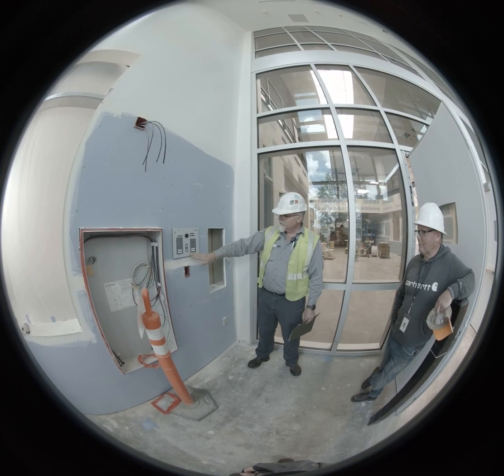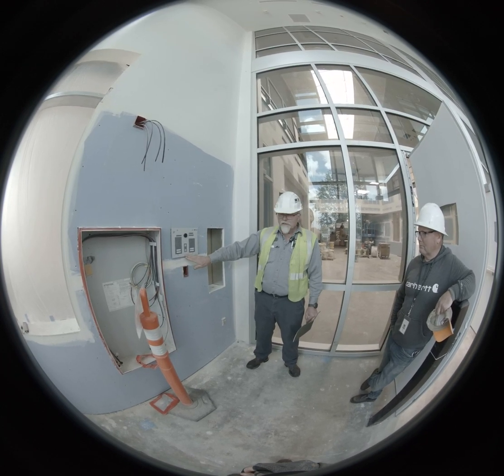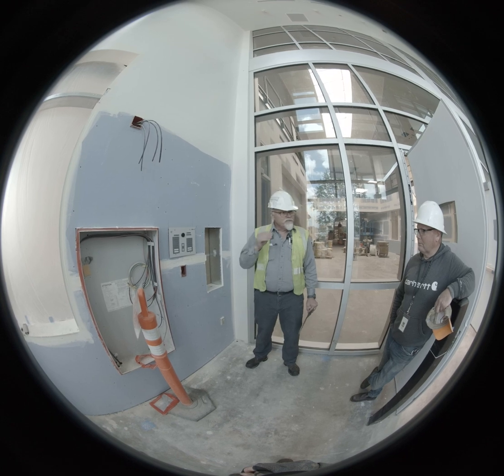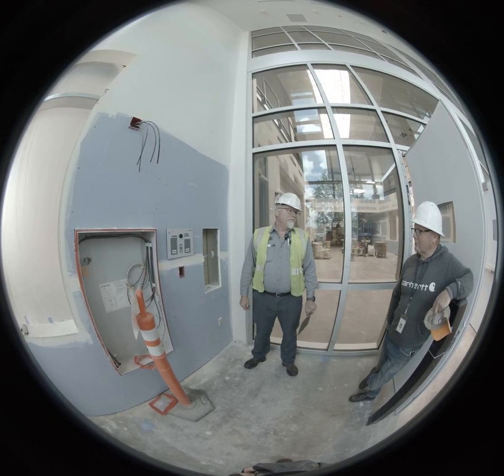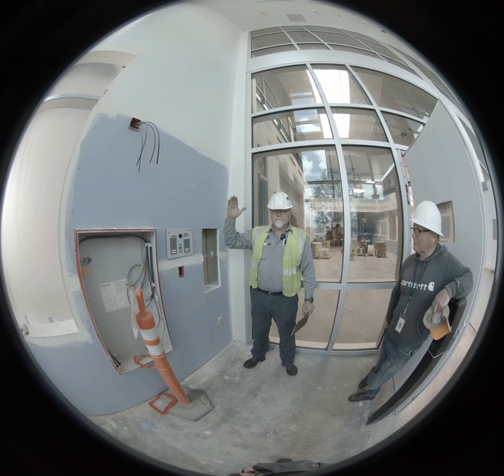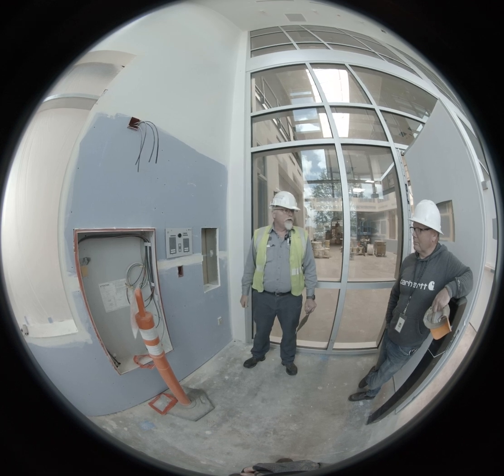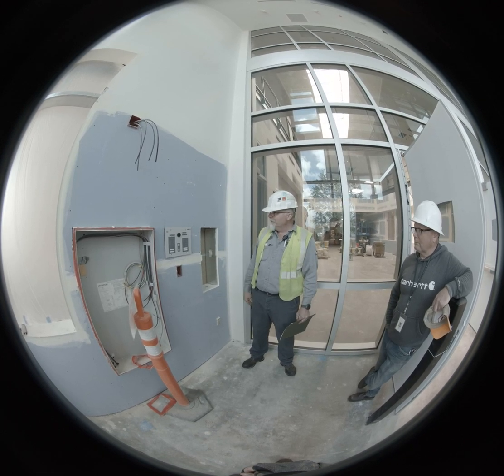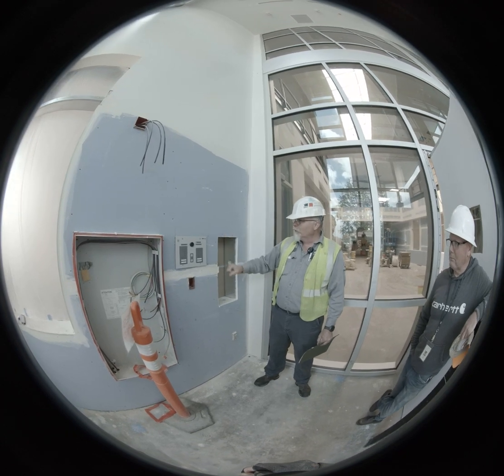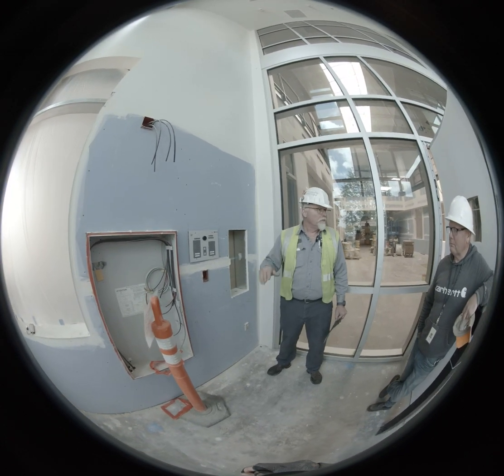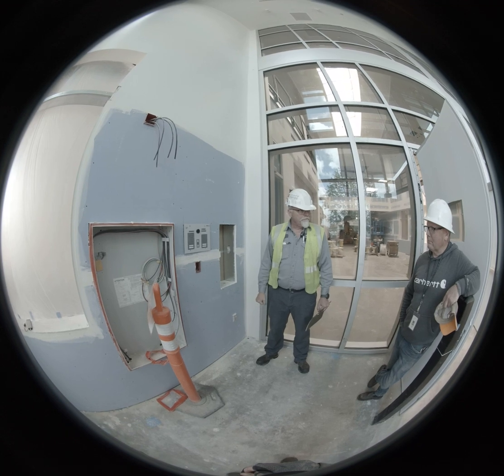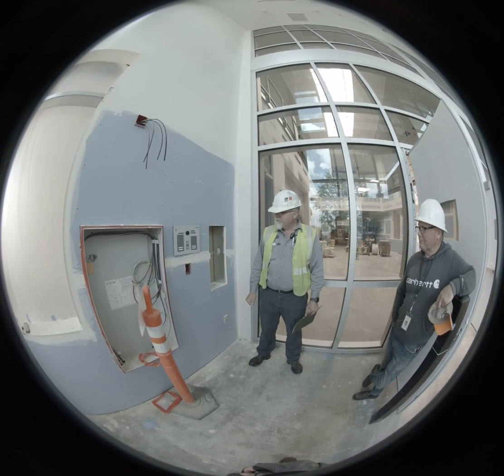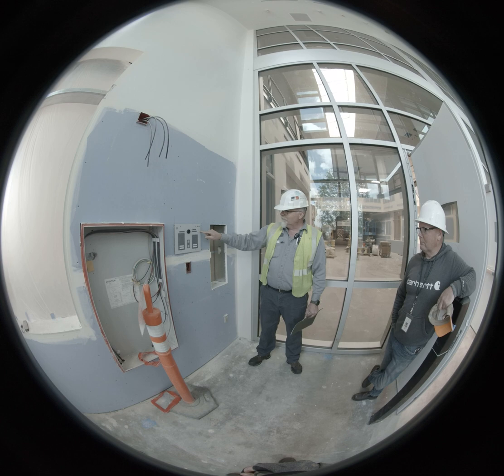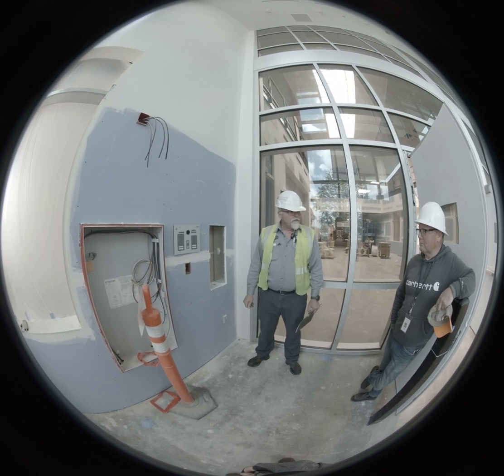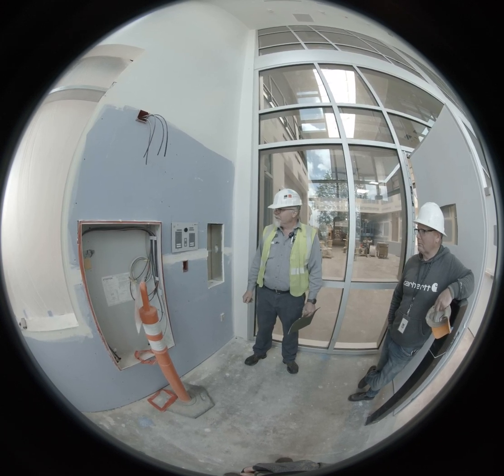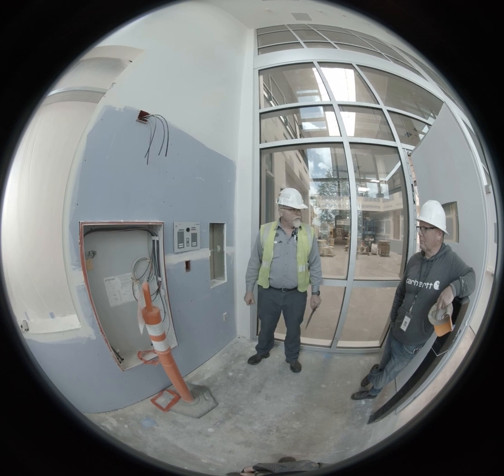And when this comes on, it's the same as on the genset itself. You have an alarm silence. You can silence it, but it may ring back. If something is coming in and out, it will re-trigger it. If another alarm comes in, say you have a pre-alarm low oil pressure and then the shutdown, those are two separate alarms, so they will trigger after each other. As long as you have the little green light on here, it tells you this thing is communicating. Of course, the EPS supplying load is that 3% we talked about earlier.